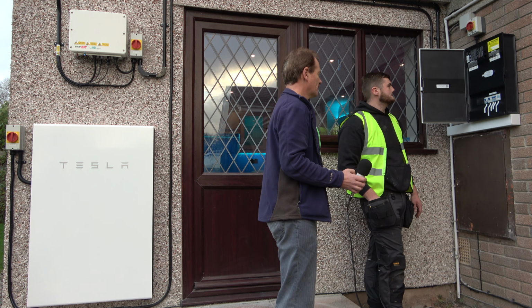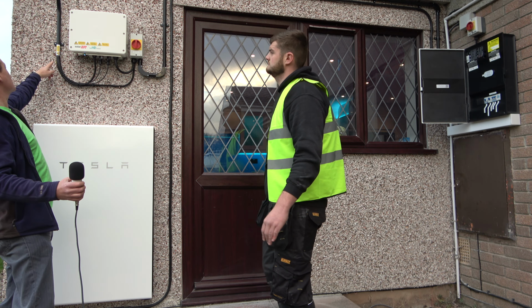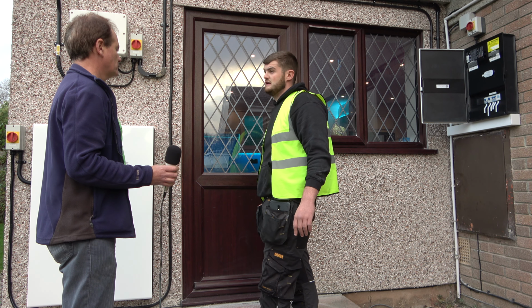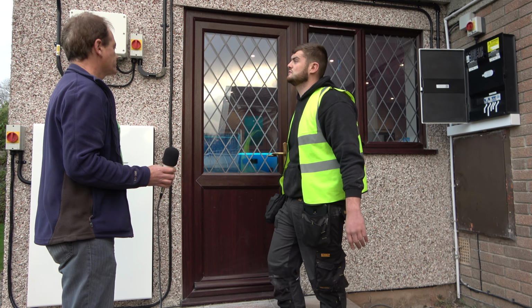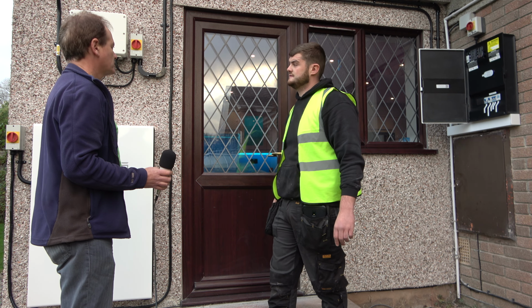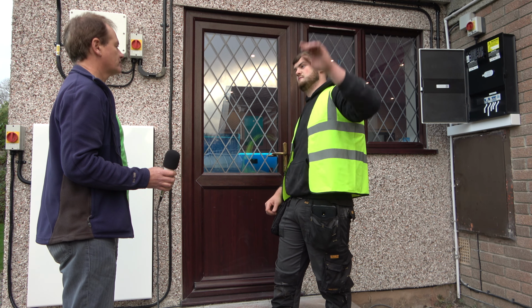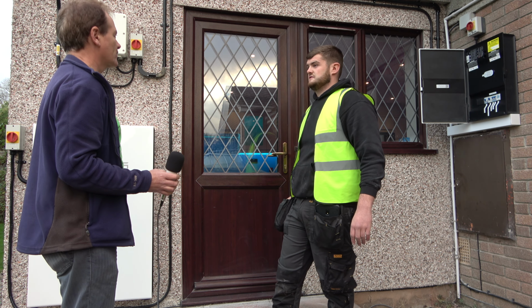Yeah. Okay. Oh, and going back to this installation, sorry, I noticed you had, there it is, an earth wire here. Yes. But it isn't connected to anything, so what's that? No, so we earth the rails up on the roof, just in case later on you want to upgrade to a different inverter, different model. Sometimes they have earth connections that need to be met. Okay. Or we would connect it if you were able to reach your panels from any Velux windows or anything like that. Right. Just so you can't touch the extraneous parts and the panels at the same time and get a belt off of it. Right, but that's not needed now. It's not needed in this case because you don't have access to that.